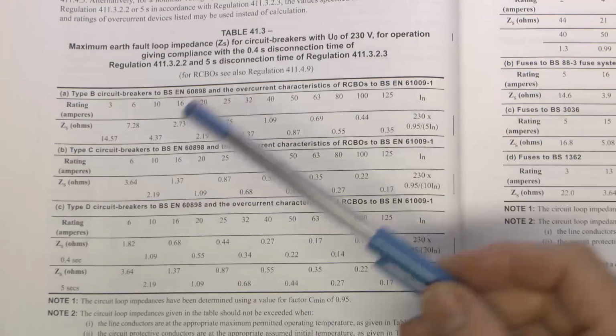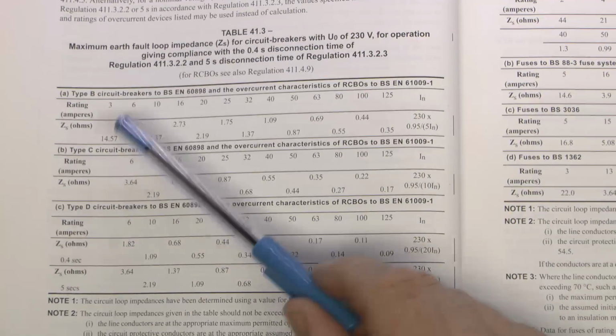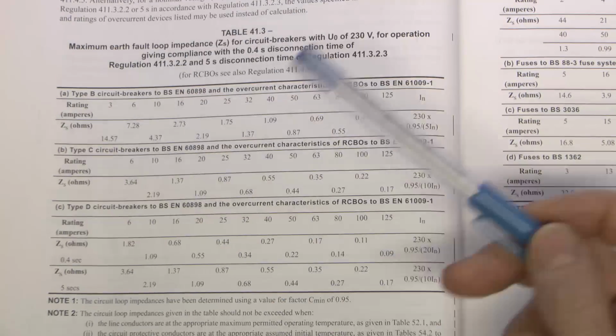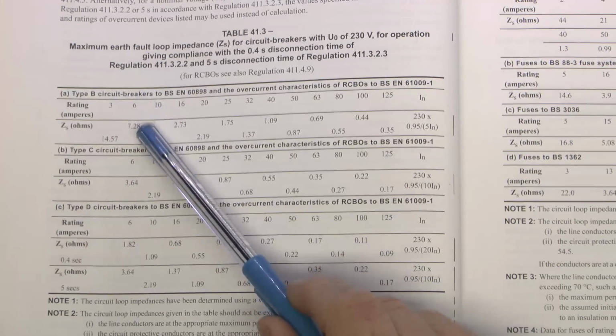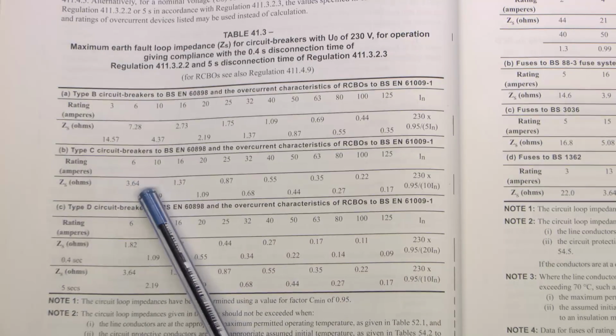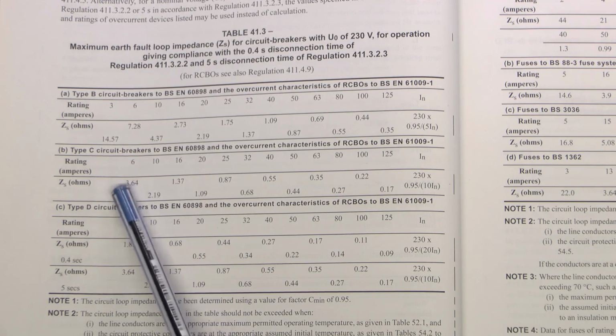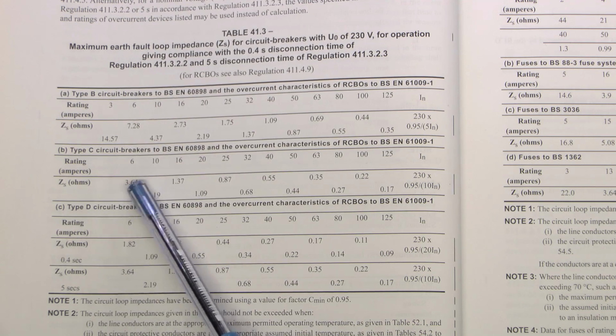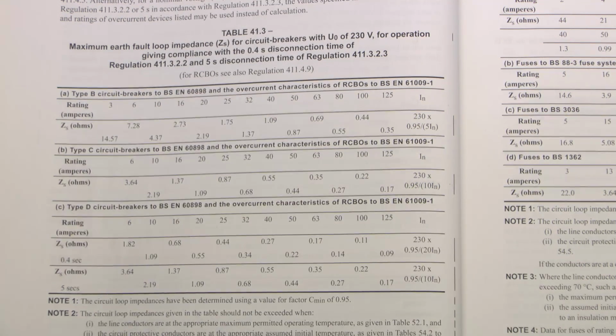So if you measure the impedance of a particular lighting circuit, for example, and found it was, say, something like 4 ohms, fairly long one, then of course fitting a type B is perfectly acceptable. But fitting a type C would not be, because the 4 ohms is greater than we've got here, so that if a fault occurs, the current that flows is not going to be sufficient to disconnect the thing within the required time. Time in this case is the 0.4 seconds, which is applicable to most circuits. And again, with an impedance of 4 ohms there, you most definitely couldn't fit a type D either, because the impedance required is a maximum of 1.8. And again, in that case, it wouldn't actually trip within the required time.